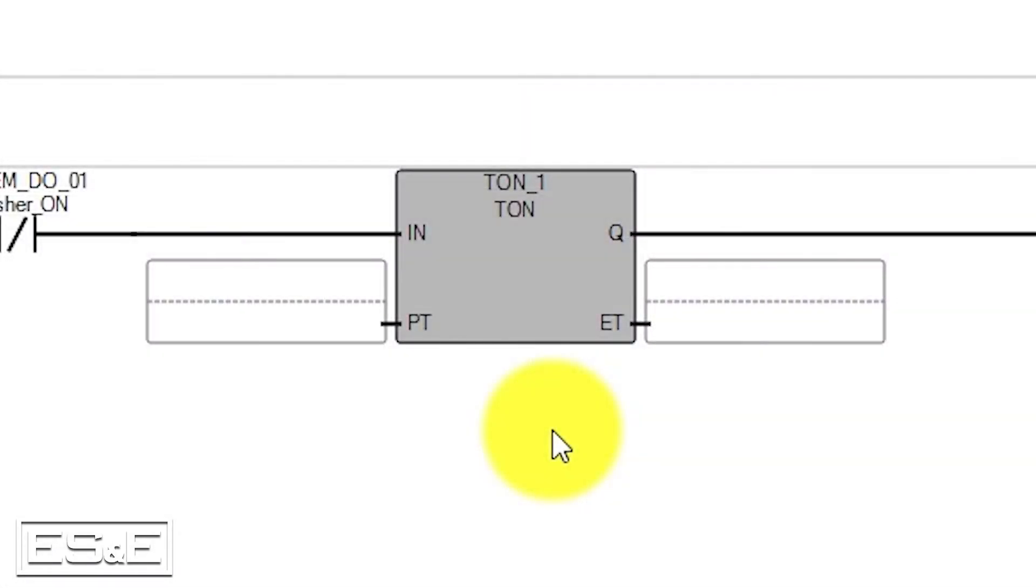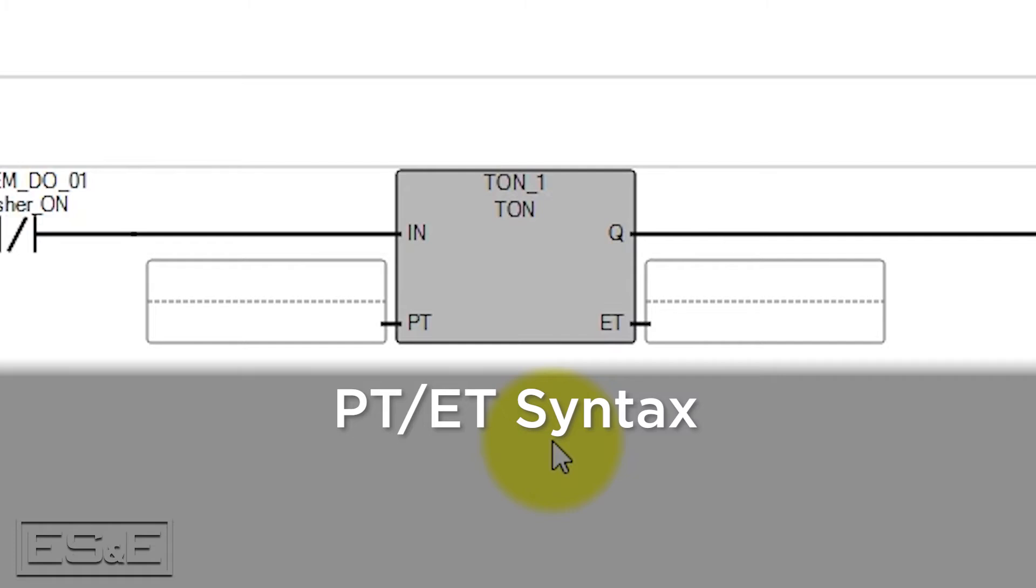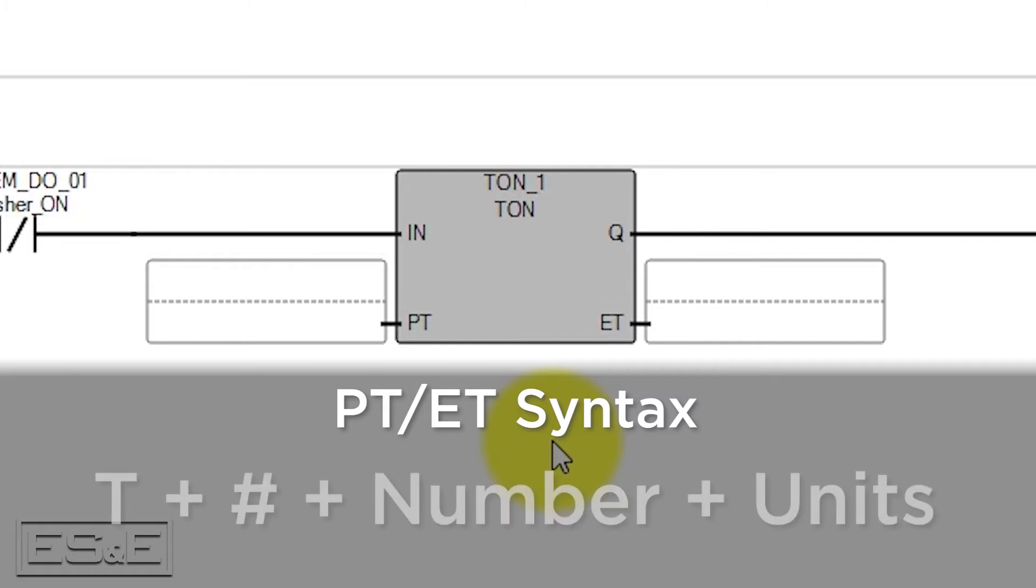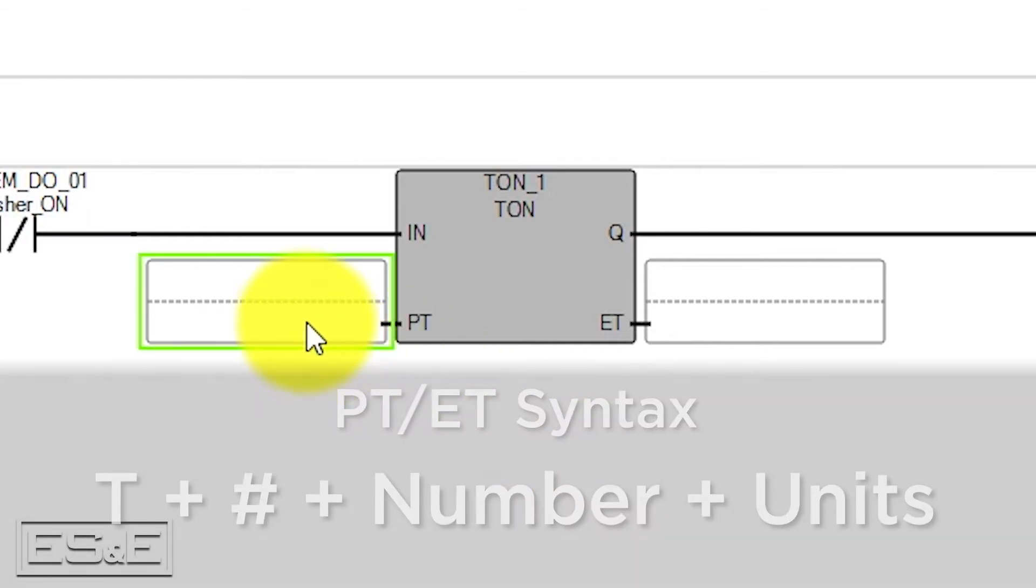The preset and elapsed time are where this instruction differs from Logix software. In CCW, PT and ET both have a time data type that have a specific syntax that starts with a T and then a pound or hashtag symbol. Then it is followed by the number and units.